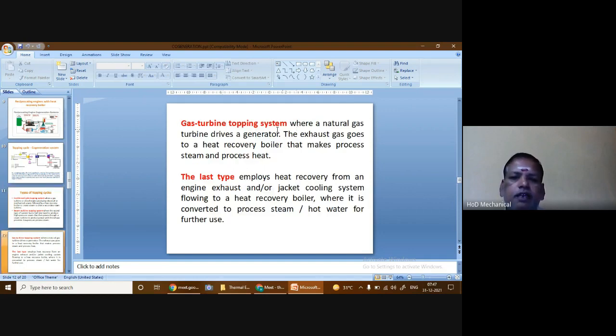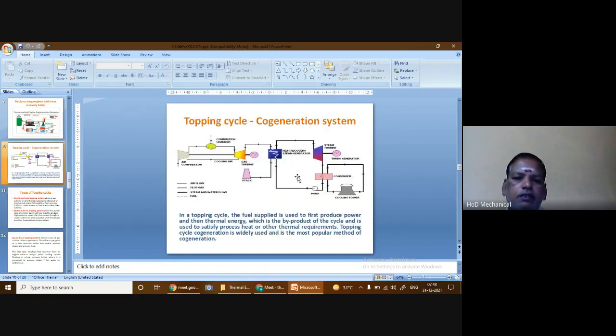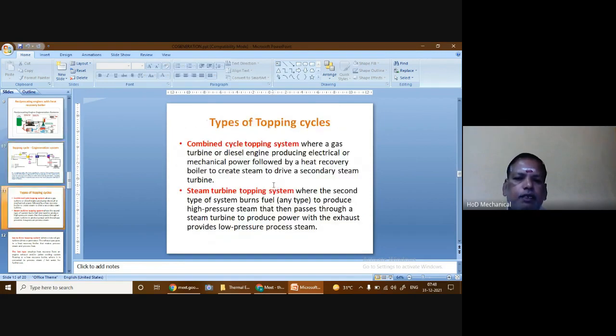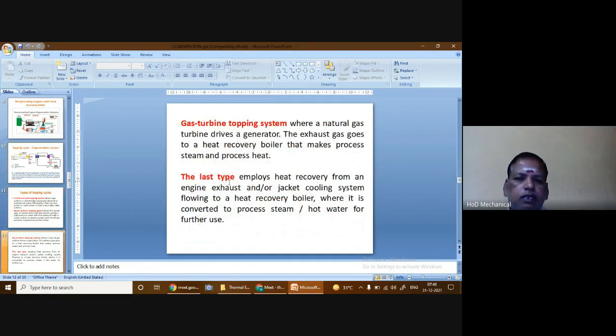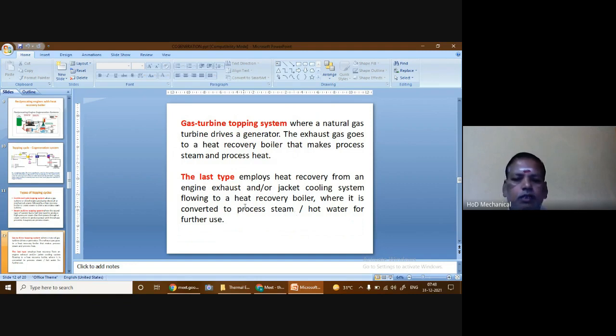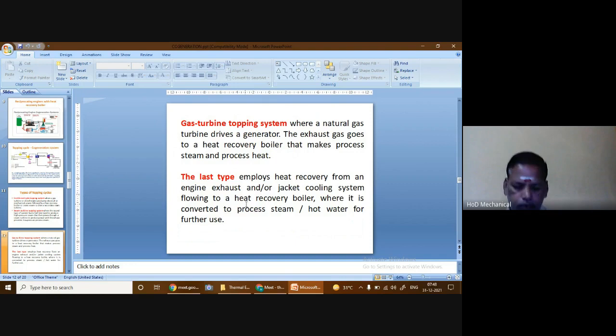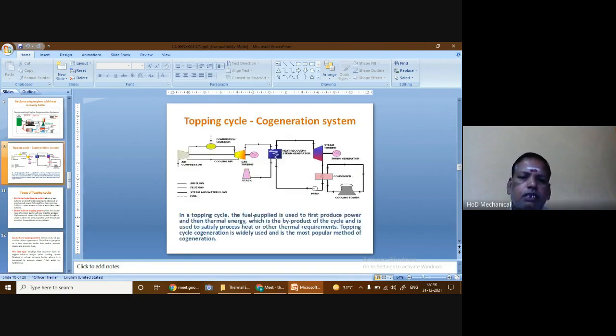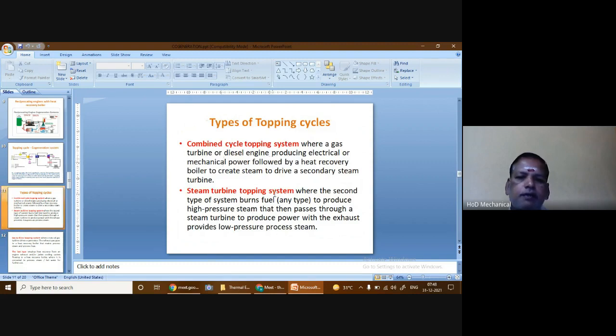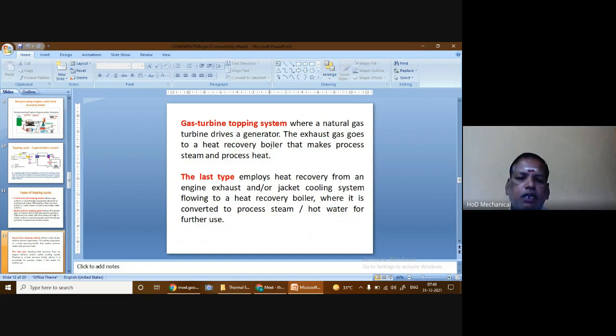The third type is the gas turbine topping system, where a natural gas turbine drives a generator and the exhaust gases go to a heat recovery boiler that produces process steam and process heat. The fourth type is the IC engine topping system, where heat is recovered from engine exhaust and the jacket cooling system, flowing to a heat recovery boiler where it is converted into process steam or hot water. So the four types of topping cycle cogeneration systems are: combined cycle, steam turbine, gas turbine, and IC engine topping systems.